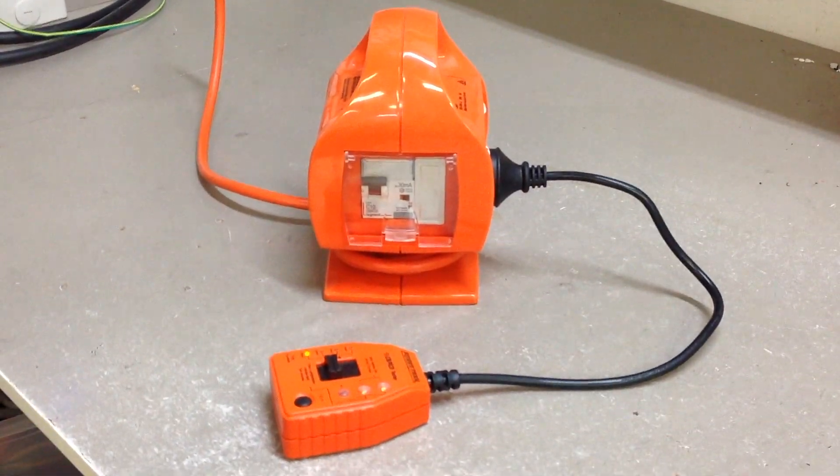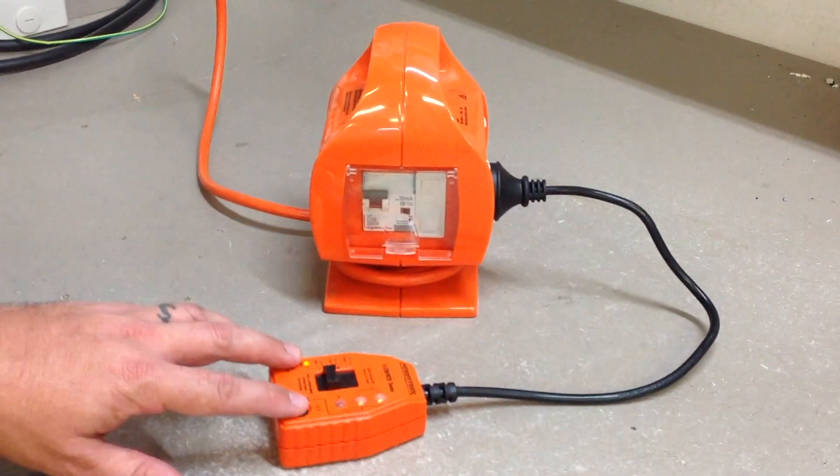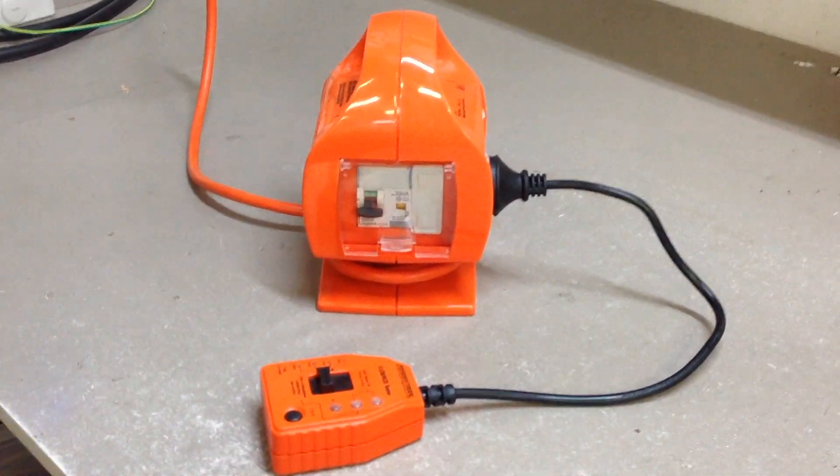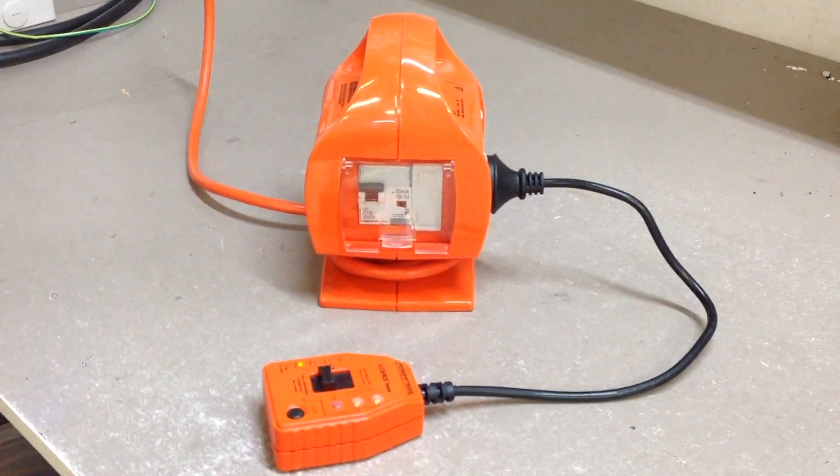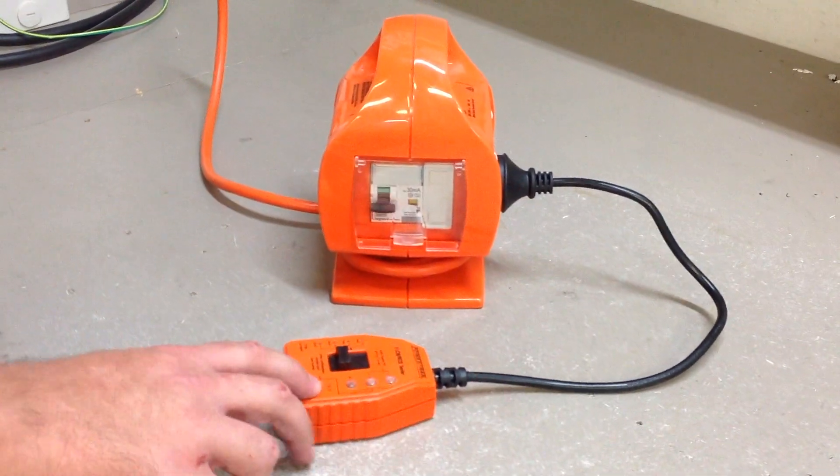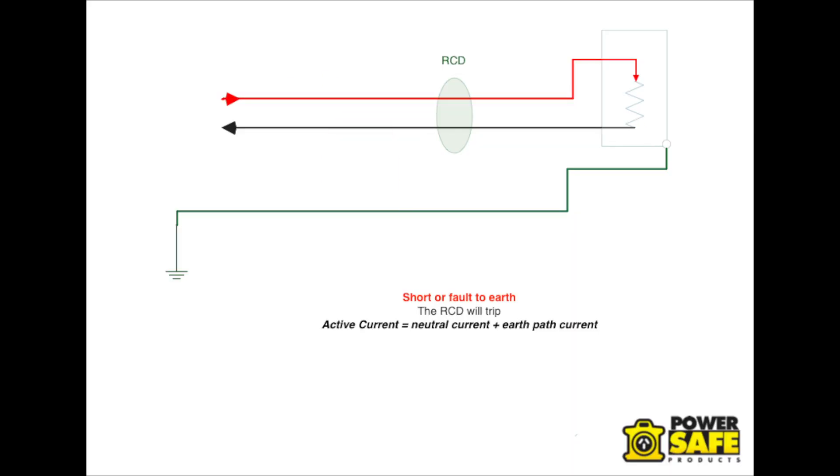If we connect the power board fitted with the RCD to a MEN or a common mains outlet and use the RCD, the RCD will trip as there is an earth path and the current flow in the active wire will have more current than the neutral wire as some current is flowing down the earth path. The RCD will trip as it will see this imbalance.